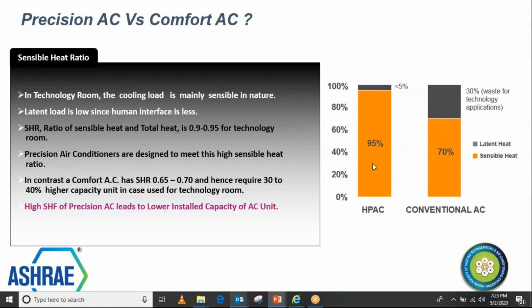So what will happen if it is a 10 TR load? If you have to install a comfort air conditioner to meet 10 TR sensible load, you will have to oversize it by 30 to 40%, because that is the gap from 70% to 100%. So to cool the 10 TR sensible load, you will have to oversize it by 30 to 40%, which means you will end up installing around 14 to 15 TR, around 14 TR capacity. This is just to meet the sensible capacity requirement. And if you go for a precision air conditioning system for the same requirement, you will obviously choose a machine with around 0.95 to 1 sensibility ratio, and you will just match the requirement. So you will not overcool it.